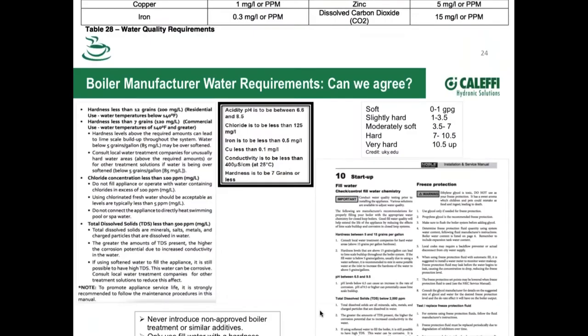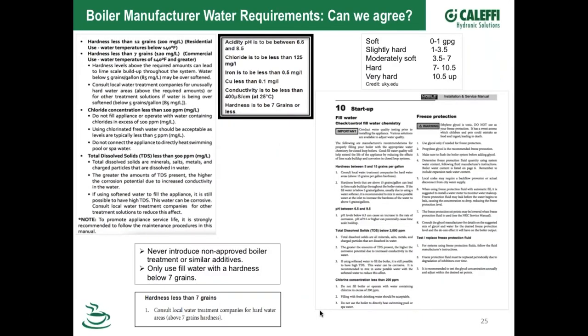This one's a little cluttered, and hopefully you don't have to read through all of these, but what I'm trying to show here is I'd hope the boiler companies could all get on the same page, because here you've got 1, 2, 3, 4, 5 different boiler manufacturers. And if you notice, one guy's saying it's got to be between 5 and 15, another guy saying below 7, another saying between this and that. This one up here has his pH between 6.6 and 8. Obviously, that 6.6 isn't going to be very good in an aluminum boiler. So everybody's just got different numbers out there.